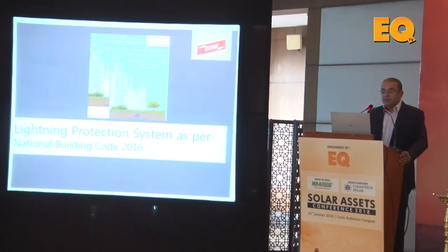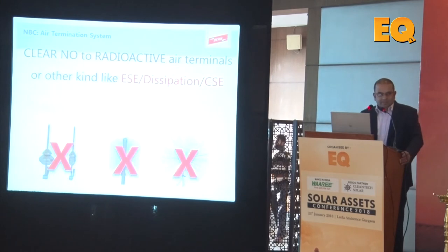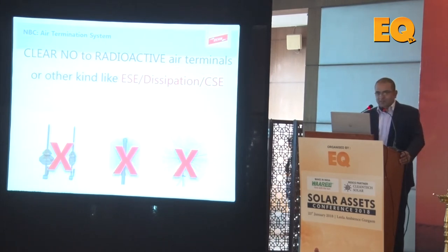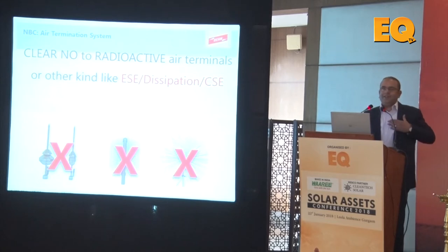The National Building Code, as I already told you, requires lightning protection. Most power plants in India use a device called ESE terminals—early streamer emission devices. They put one rod somewhere in the corner of the whole power plant, assuming it will protect the whole plant. That logic doesn't work. You have to use scientific, rational reasoning to select the right positioning and right number of lightning protection rods, and not rely on such magical devices because they simply do not work.